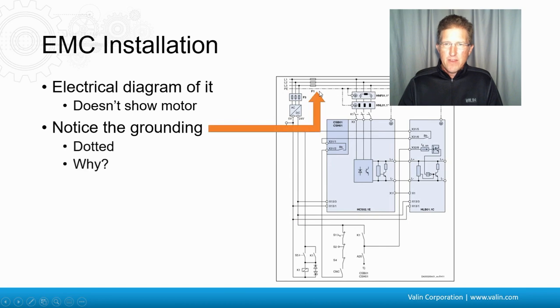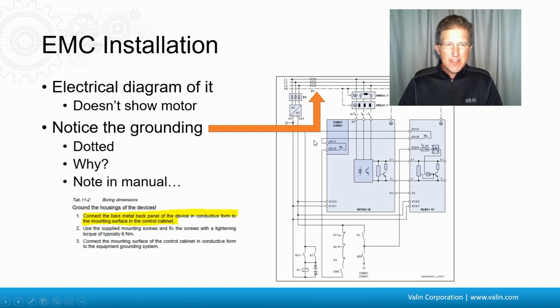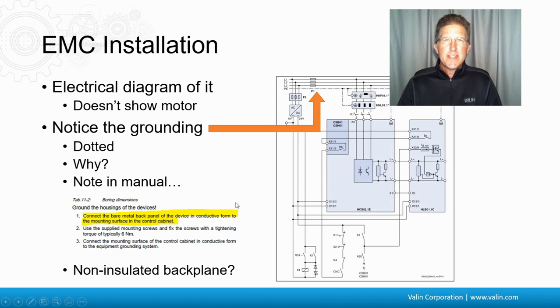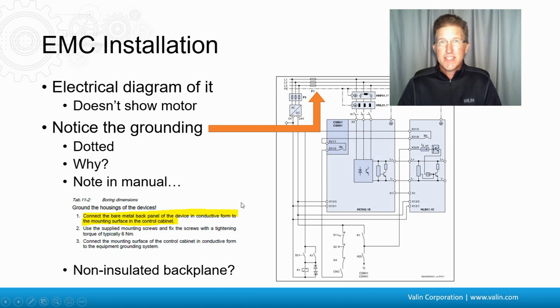Notice the grounding in the diagram — it's shown as dotted. There's a note in the manual that says: connect the bare metal back panel of the device in conductive form to the mounting surface in the control cabinet. That's a non-insulated backplane. Again, the fine print concepts are very important — simple concepts, but most people overlook them. I've solved electrical noise issues many times just by attaching the R-clamp or P-clamp of the motor cable to the drive and telling them to take the paint off the panel behind the drive.